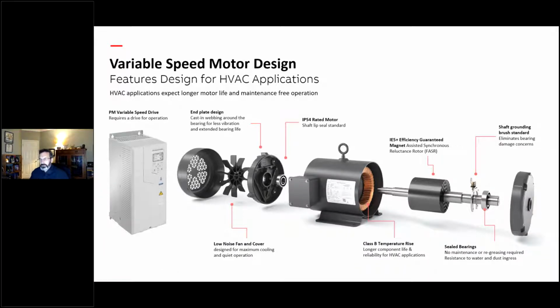I'll show you a graphic of what that looks like. So this motor design has that as standard, but it's highly recommended for HVAC motors, any design, if you're going to put it on a drive. From a safe system standpoint, either electrically isolate with ceramic bearings or do a shaft grounding brush. I like shaft grounding brushes because it takes any of that common mode voltage and current and shunts it right to ground. A ceramic bearing electrically isolates the bearing and protects the bearing, but that current still has to go somewhere, and it's going to go into the driven equipment.